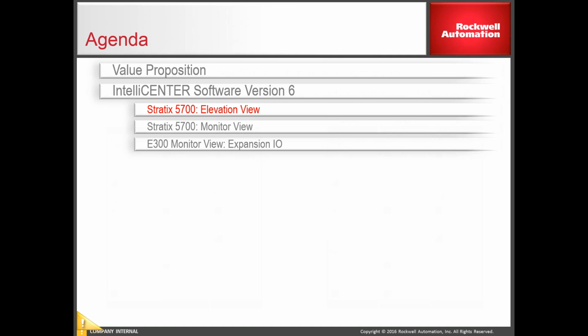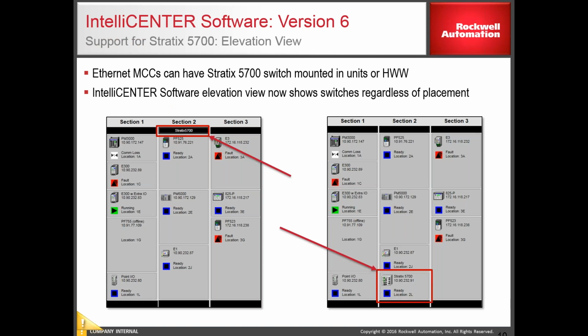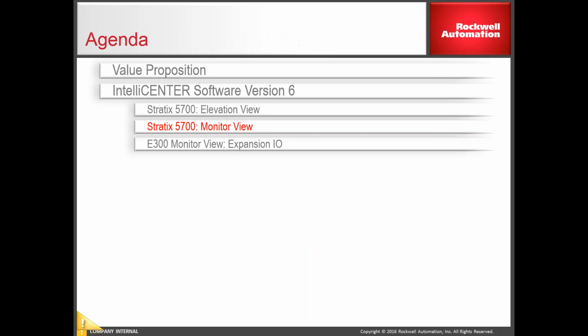So what's new with version 6? So one, with IntelliCENTER software, we've got Stratix switches throughout the MCC to get all the devices on the Ethernet network, right? And initially, when we first launched IntelliCENTER, we would put a Stratix switch in every vertical section, right? So if you had 10 sections, you end up with 10 Stratix switches, which is a lot of switches, right? And it's overkill. So we've optimized that. So now we'll put a Stratix switch in a bucket, and we can have up to 30 ports. So you can have one switch for 8 or 9 different sections, right? So the new thing here is that now that Stratix switch shows up in this elevation, whether it's in the horizontal wireway or whether it's in one of the units, okay?